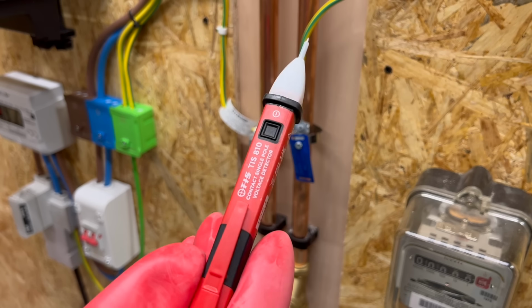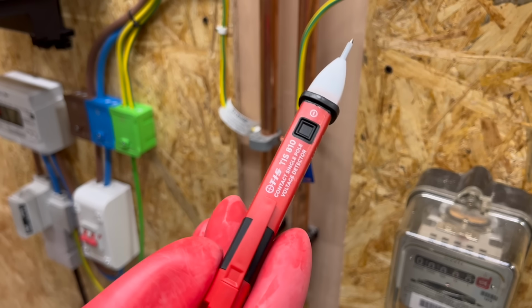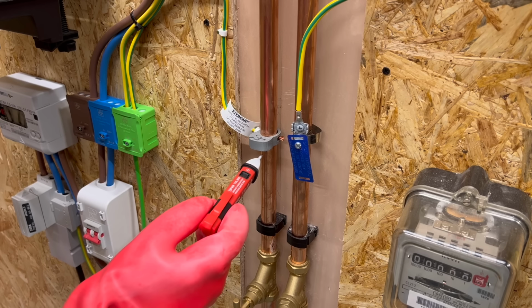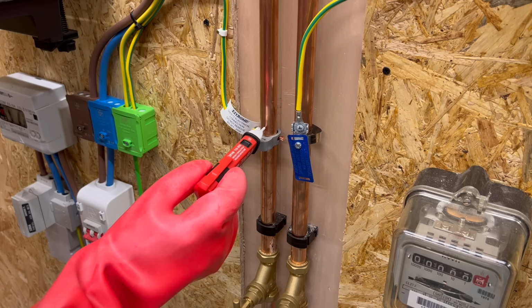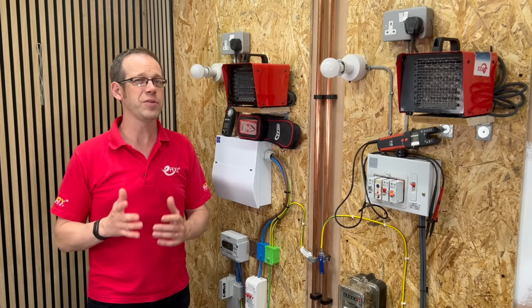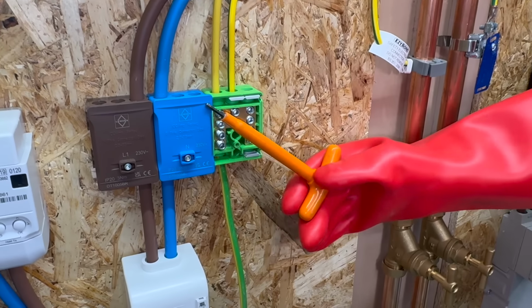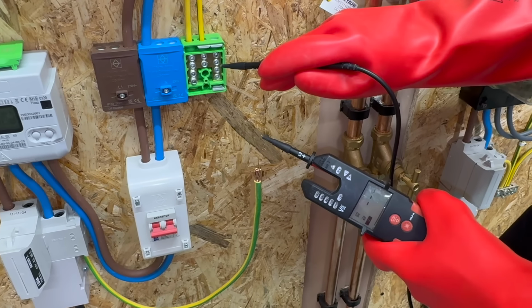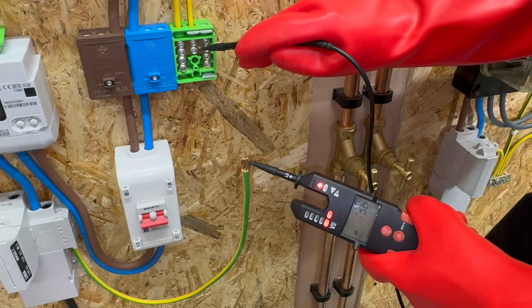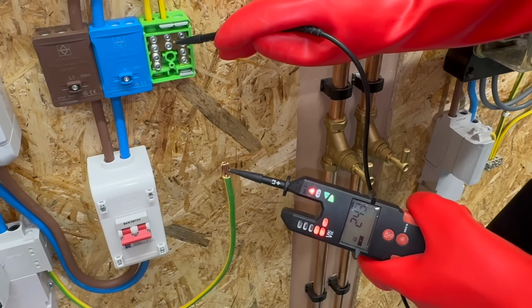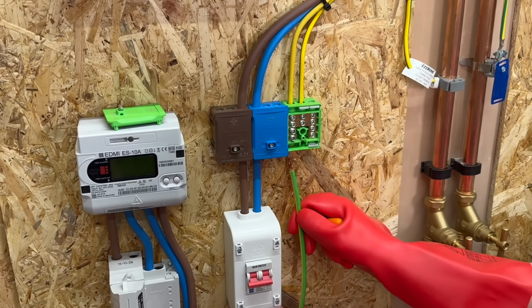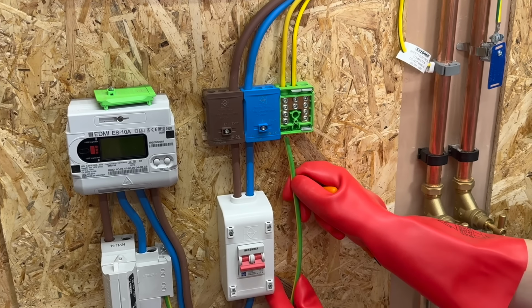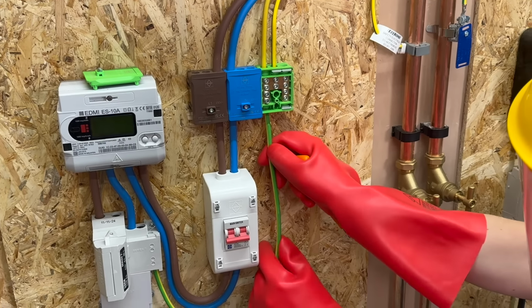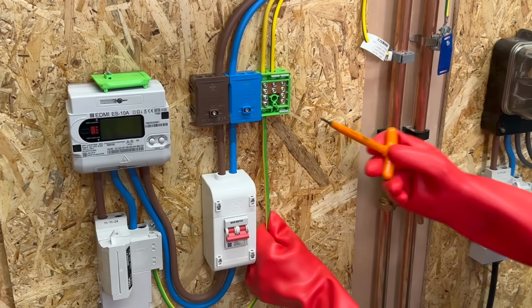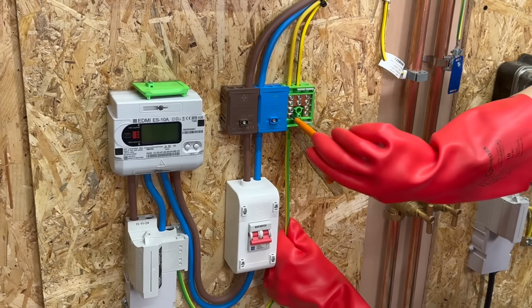To add an extra layer of protection to the process, you could get yourself one of these contact voltage detectors and pop it onto the earth metalwork in the property, both before and after disconnecting the earthing conductor. To be absolutely sure, you could very carefully, while wearing protective gloves and other appropriate PPE, disconnect the main earthing conductor and measure voltage between it and the main earthing terminal. If there's a significant voltage there, then very carefully simply reconnect it and contact the DSO to come out and investigate. Remember, if there is a significant current flowing through the protective conductor system when you disconnect and reconnect the conductor, it could create an arc, so make sure you're wearing all the relevant PPE before you do it.